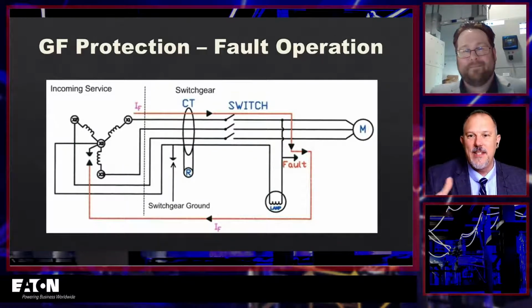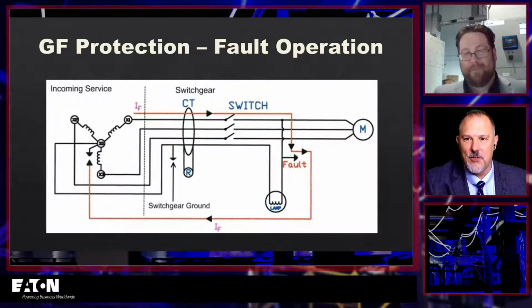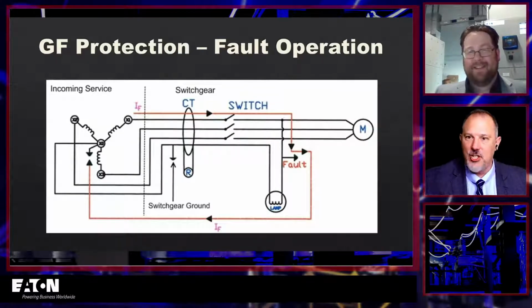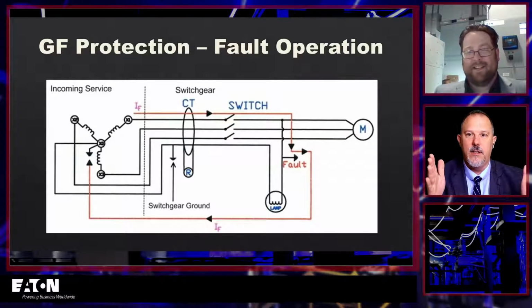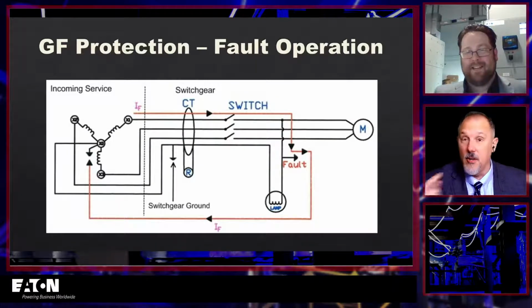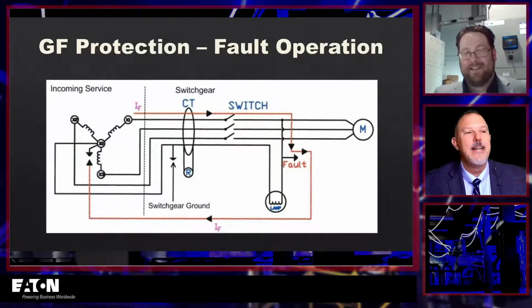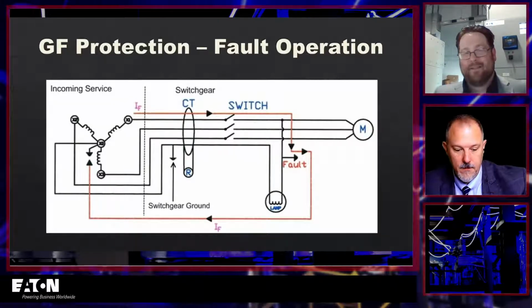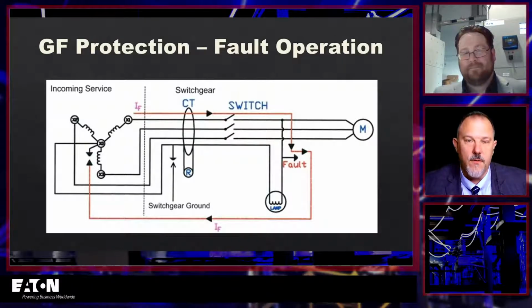If I want to increase the amount of current flowing through a grounding electrode conductor or equipment grounding conductor, I shorten it up. I make it 10 foot instead of 100 foot, and I'll drive a lot more current through the equipment grounding conductor. And then I was told to go read the Soares Book on Grounding. So then I talked to another individual, and they said it has nothing to do with fault current flowing through the equipment grounding conductor. This gentleman's on panel 5.